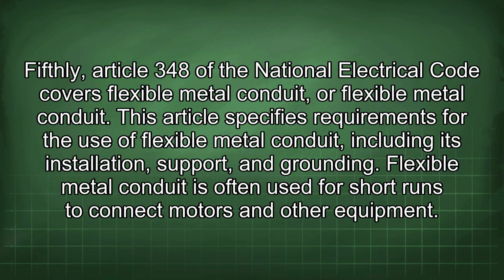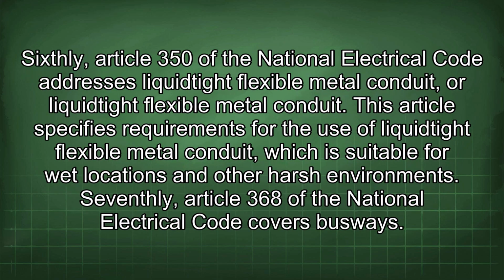Fifthly, Article 348 of the National Electrical Code covers flexible metal conduit. This article specifies requirements for the use of flexible metal conduit, including its installation, support, and grounding. Flexible metal conduit is often used for short runs to connect motors and other equipment. Sixthly, Article 350 of the National Electrical Code addresses liquidtight flexible metal conduit.